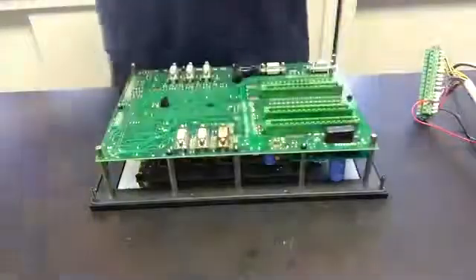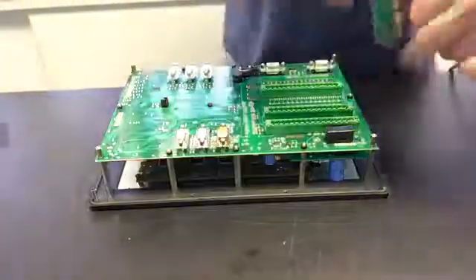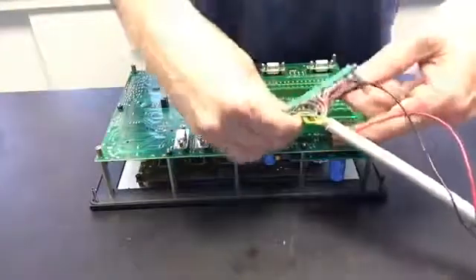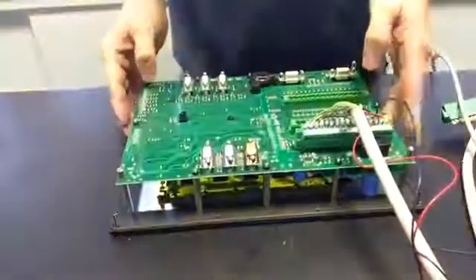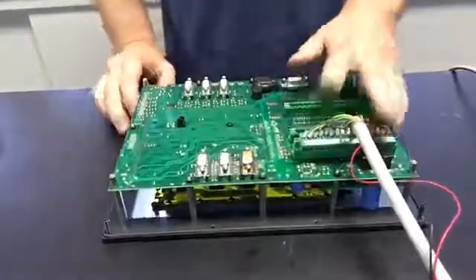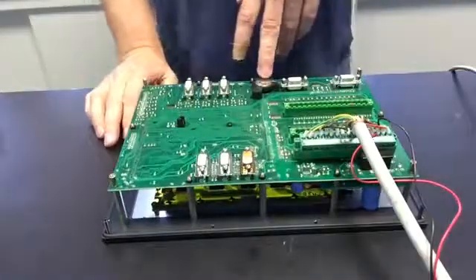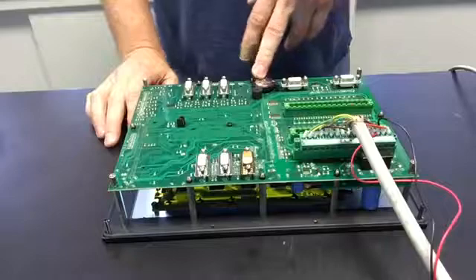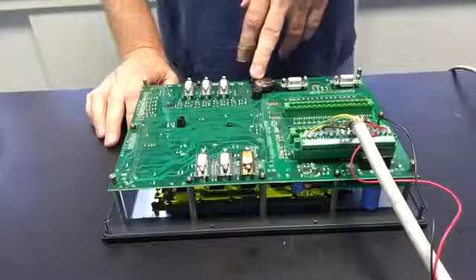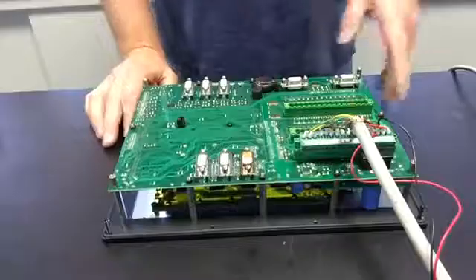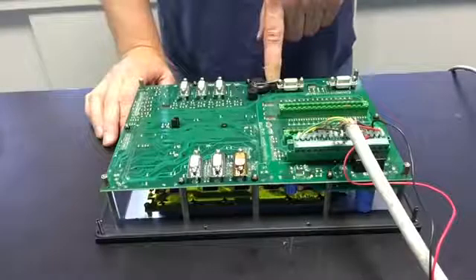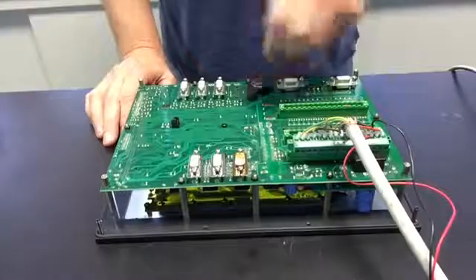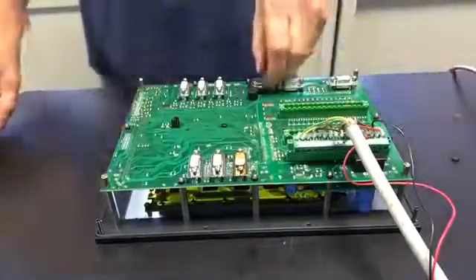You remove the back cover, and then what you want to do is reconnect the power to the control. See my control is turned back on. It's important that the power connection is put back before removing the battery. If you don't, you certainly lose any programs that you have saved in the active memory. After you've connected the power, there's a jumper right here next to the battery. We're going to remove that jumper before removing the battery.